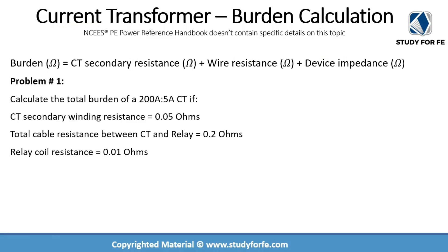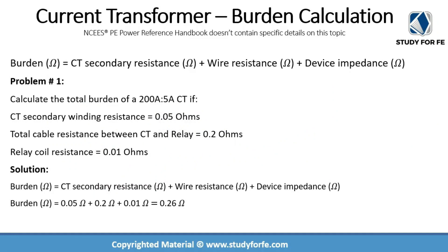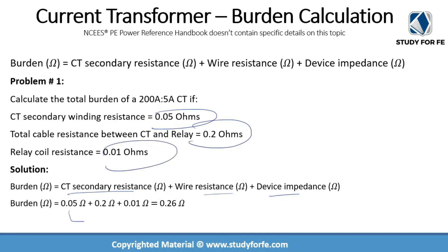Let us take a look at a practice problem. We are asked to calculate the total burden of a 200 A to 5 A CT. We are told the CT secondary winding resistance, the total cable resistance between the CT and the relay, and the relay coil resistance. The burden is the sum of CT secondary resistance plus wire resistance plus device impedance. Adding all three values provided gives a total burden of 0.26 ohms.